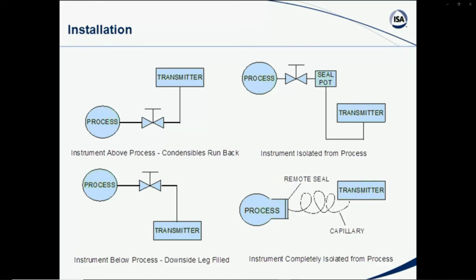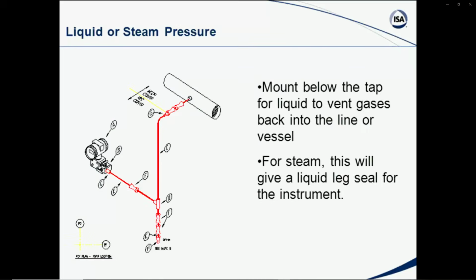But these are a way to isolate the instrument or transmitter from the process to avoid high temperature, avoid corrosive gases or liquids, to stay away from sludge or slurries, to keep the leads from plugging up. So these are all methods of installation. This is like an installation detail. I just show this to give credibility to the fact that this is on liquid or steam pressure perhaps, and here is our down leg, and our transmitter is effectively isolated from the process.